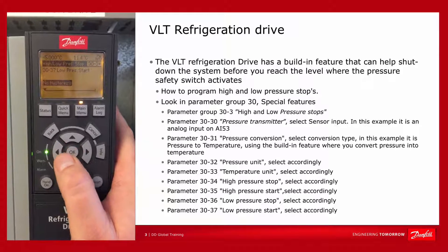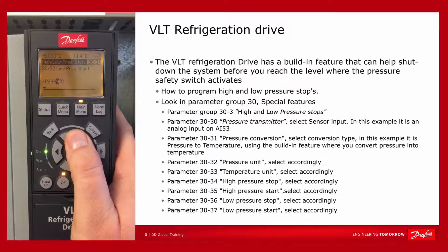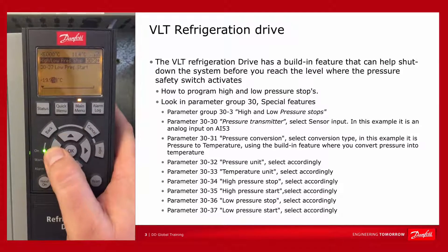Then in parameter 30.37, we will program the temperature at which we will allow the system to start running again after a low pressure stop.